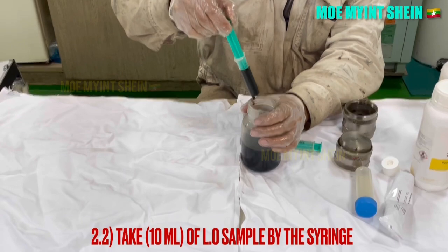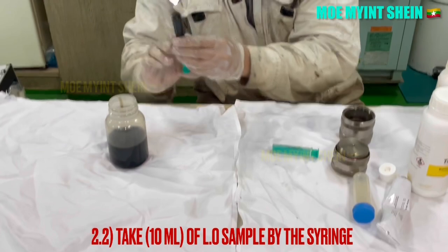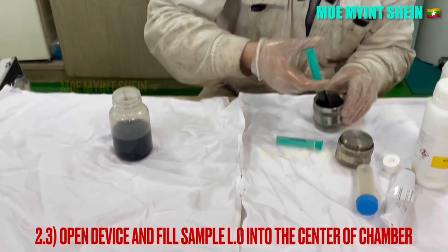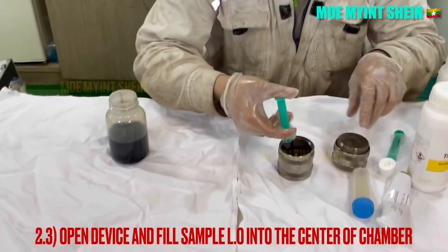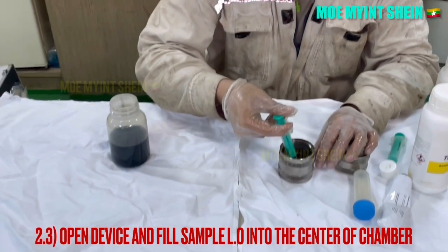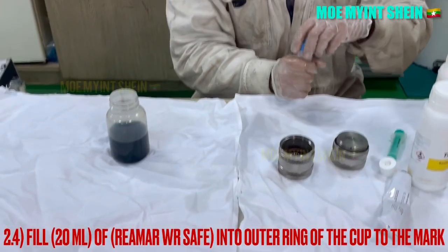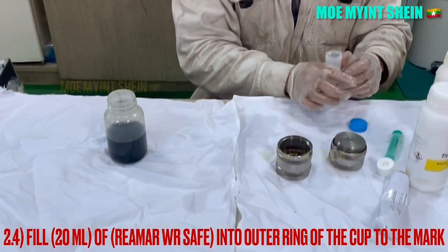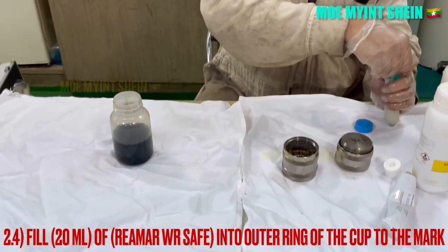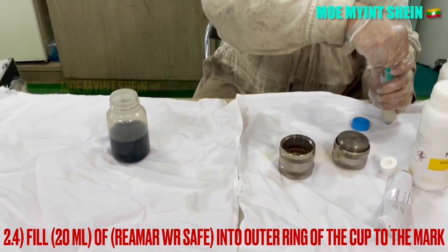And then, take 10 ml of lube oil sample by syringe. Open the device and fill the sample lube oil into the center of the chamber. Fill 20 ml of REAMAR WR SAFE into the outer ring of the device to the mark.